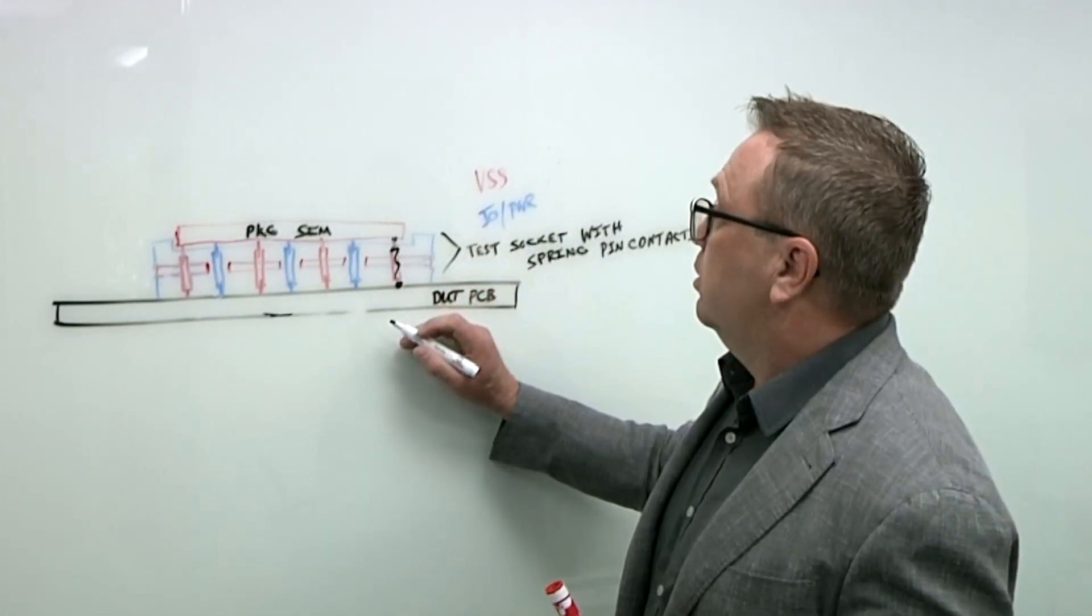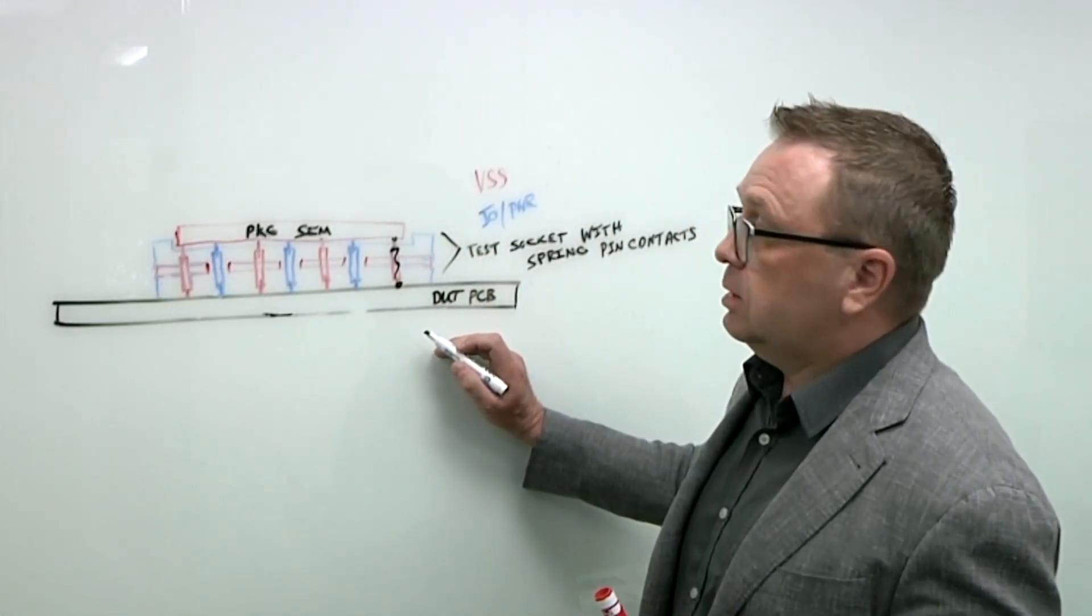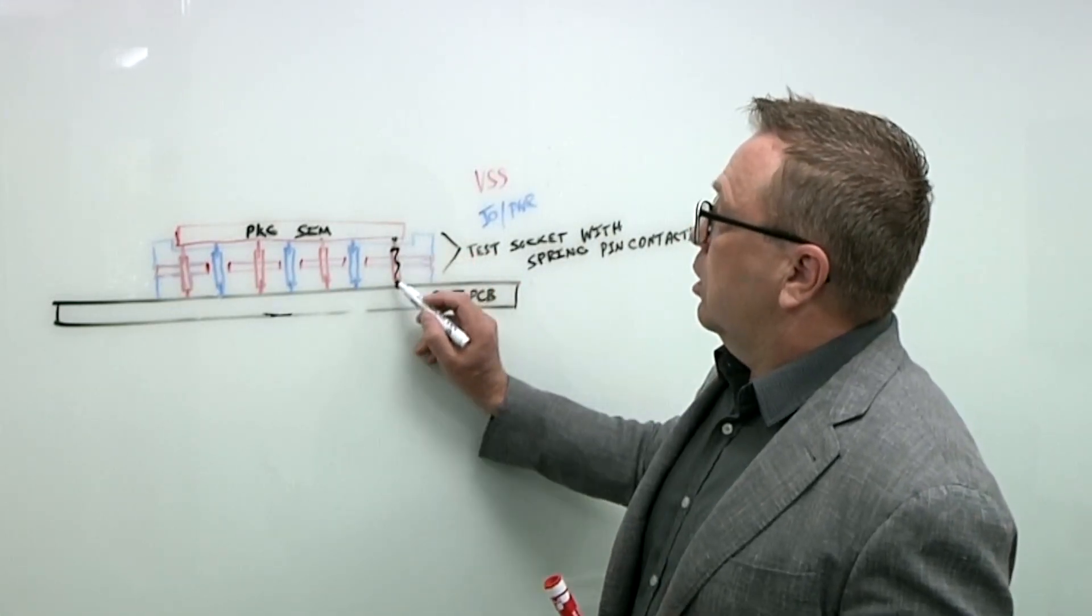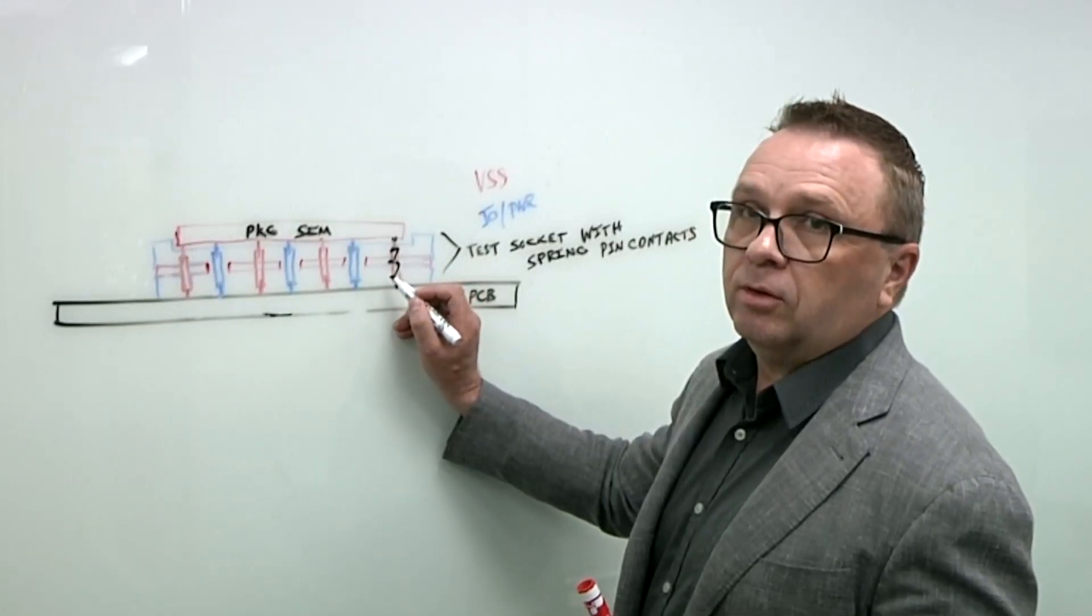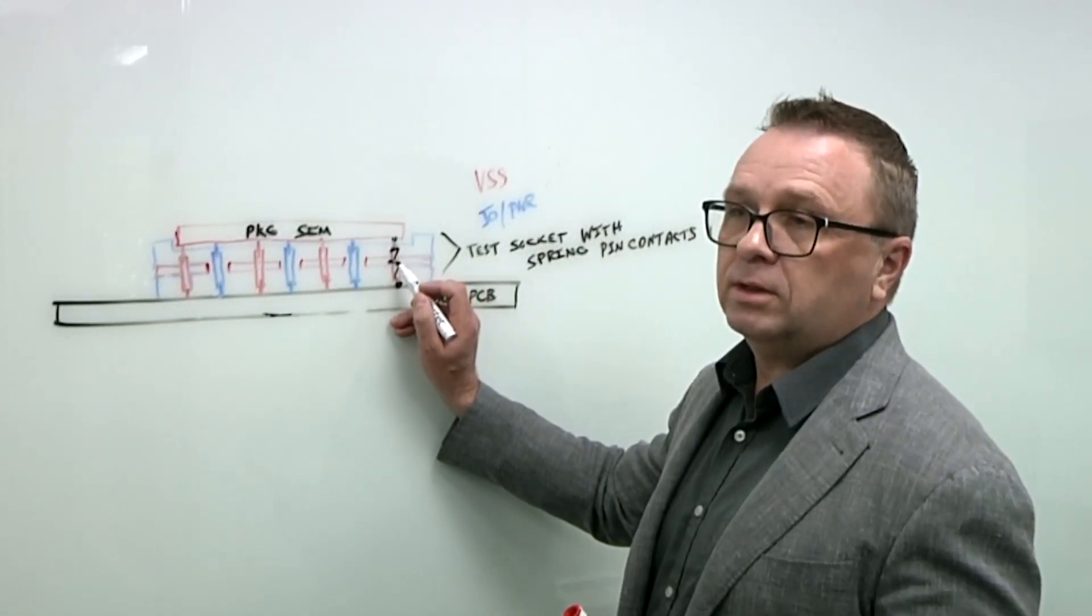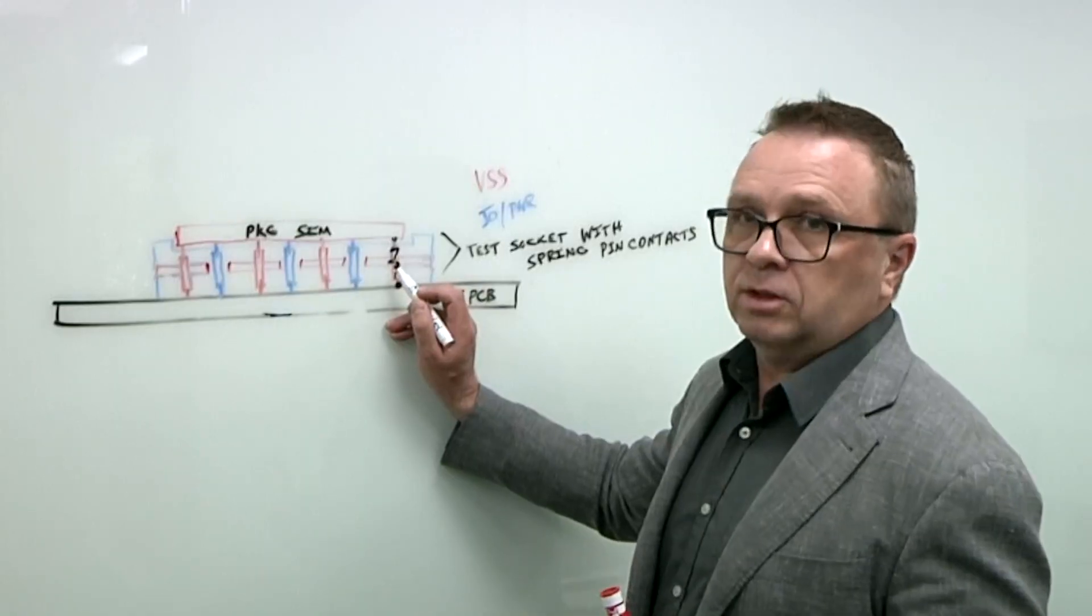Now with the addition of the coaxial shield test, we also need to make sure that this shield is performing that there's good contact between the ground pin and the shield. Otherwise, the shield performance is degraded.